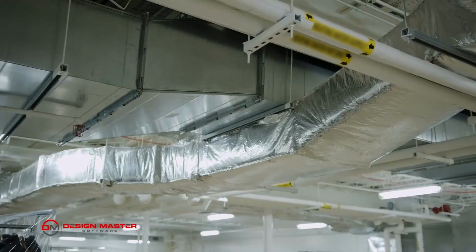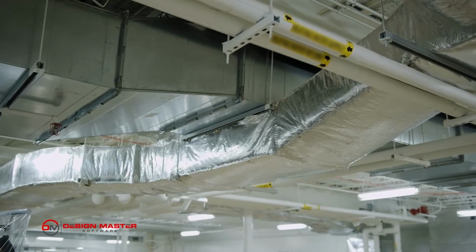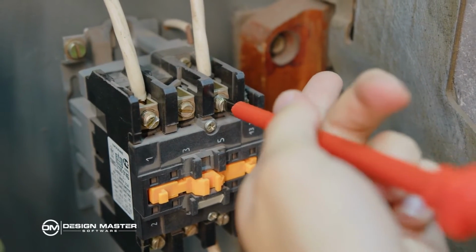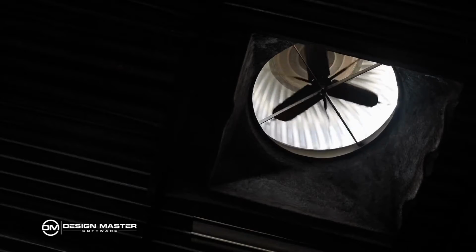So why do electrical engineers care about this? Well, the issue is this. Subducts are required to run continuously. And for years, that simply meant you provide power and you don't provide a switch other than the safety disconnect. And so the fan would run continuously. Later, interpretations by the fire marshals was that continuously also meant during a power outage, which makes sense. The subduct concept really doesn't work unless the air is flowing. And so having a power outage and the fan continuing to run makes sense.